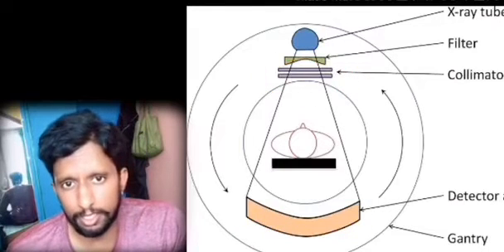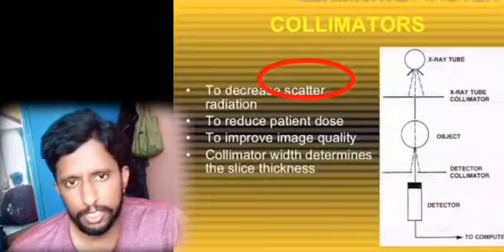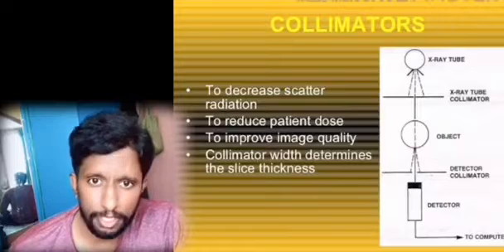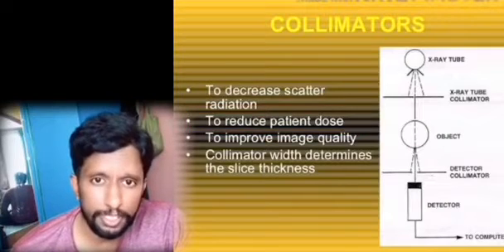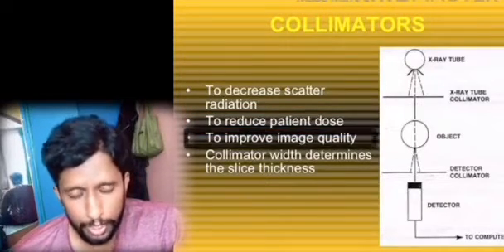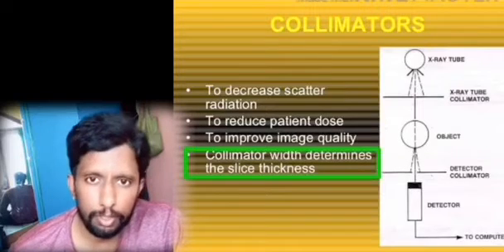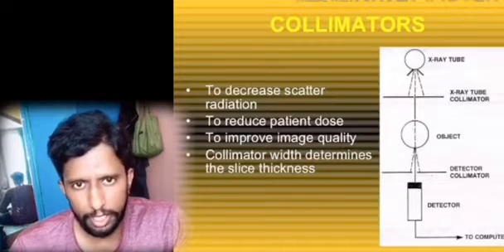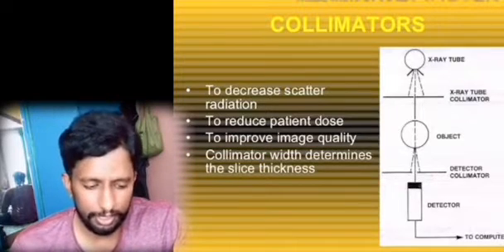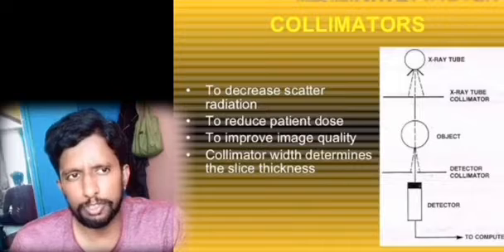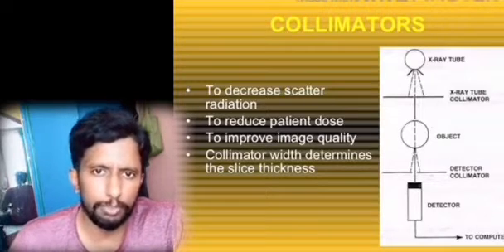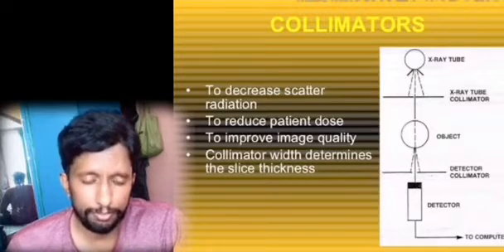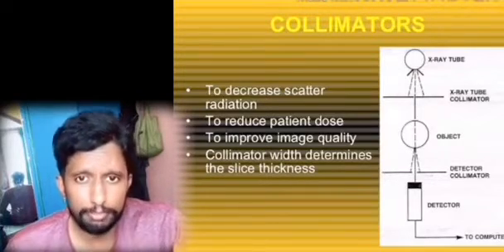The CT collimator has four functions: first, to decrease scatter radiation; second, to reduce patient dose; third, to improve image quality; and fourth, the collimator width determines the size and thickness of the slice — this is called collimation.